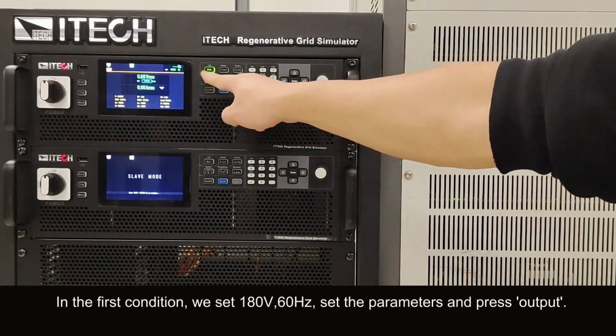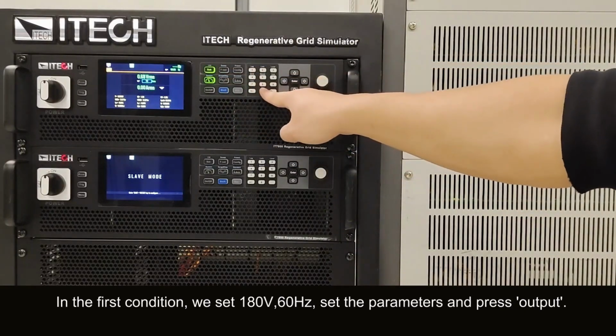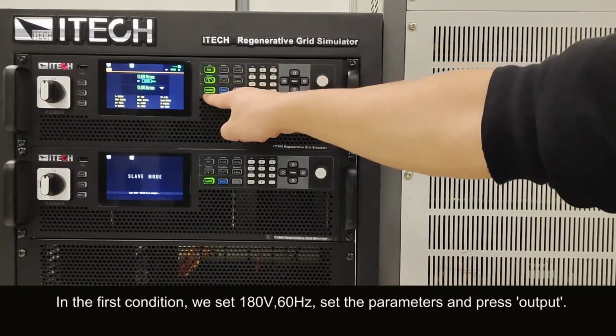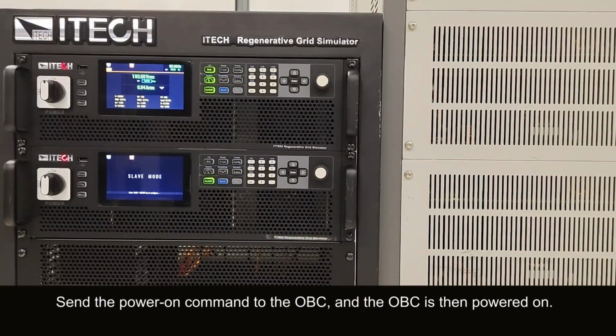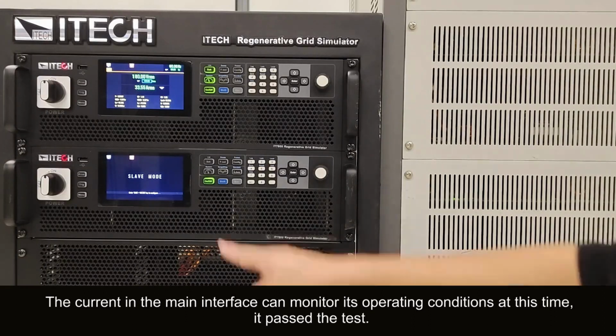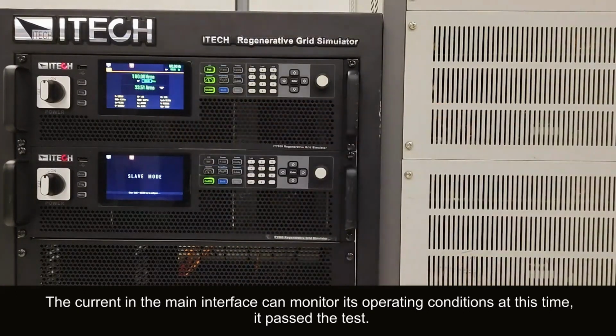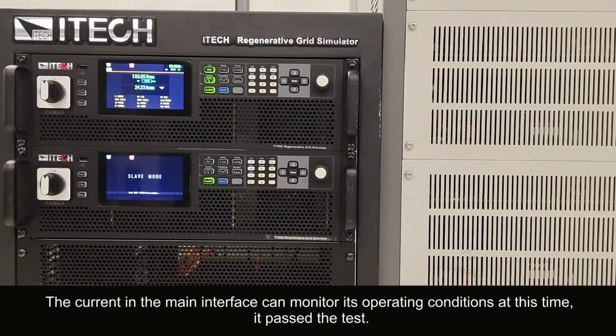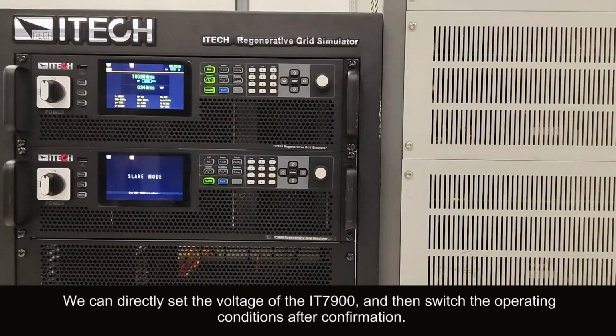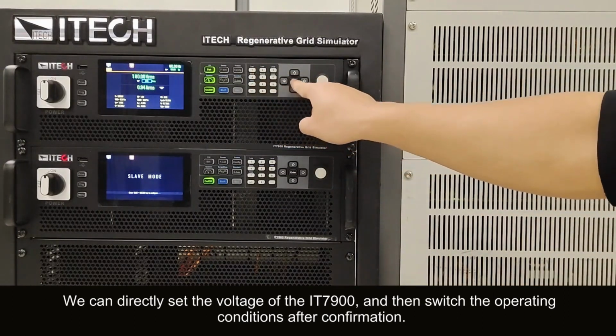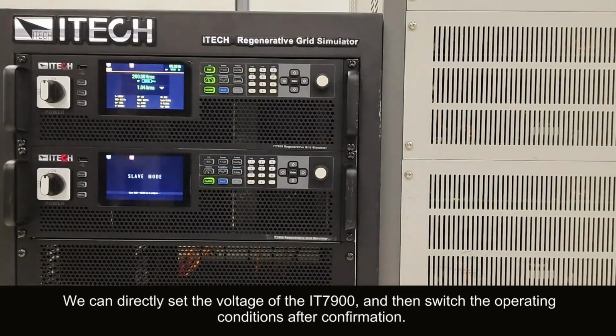In the first condition, we set 180V, 60 Hz, set the parameters and press output. Send the power on command to the OBC, and the OBC is then powered on. The current in the main interface can monitor its operating conditions. At this time, it passed the test. We can directly set the voltage of the IT7900, and then switch the operating conditions after confirmation.